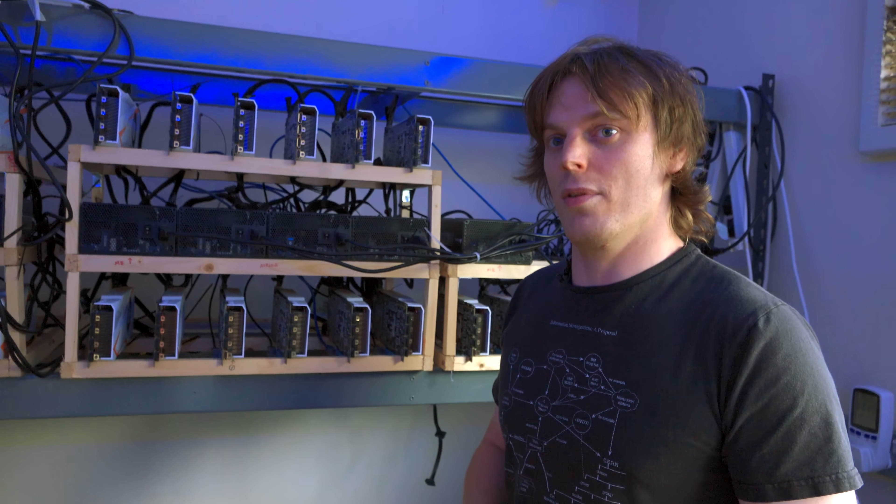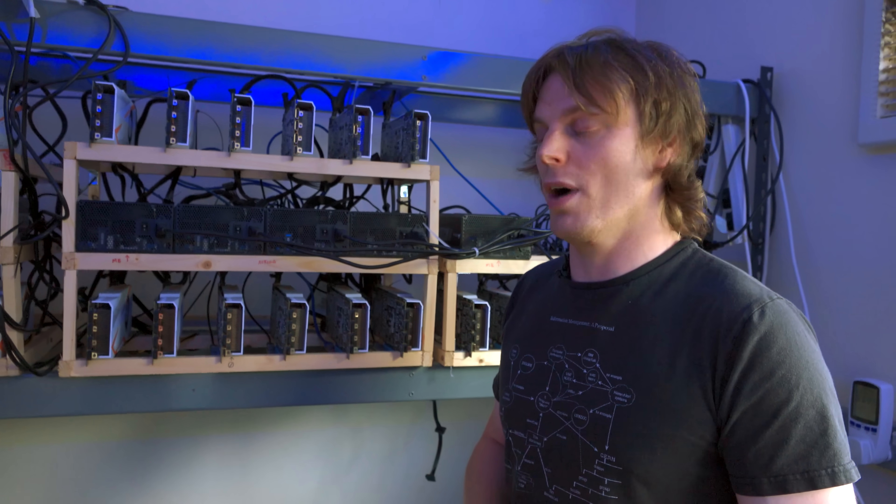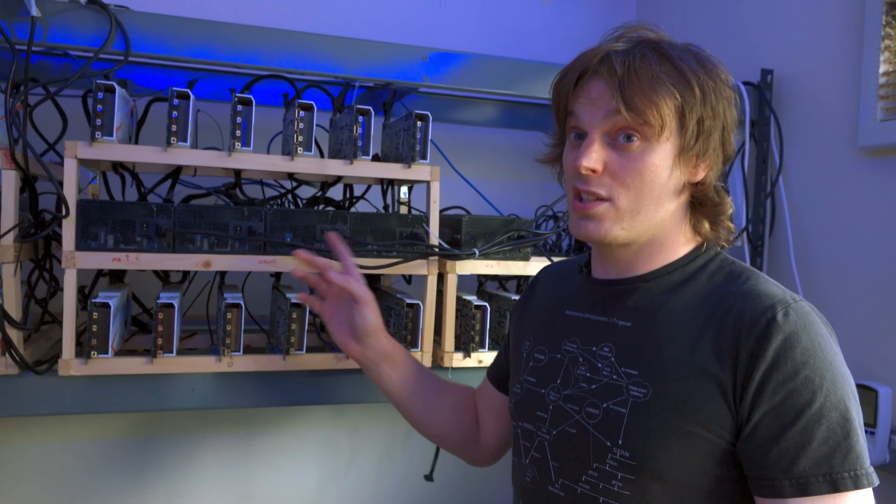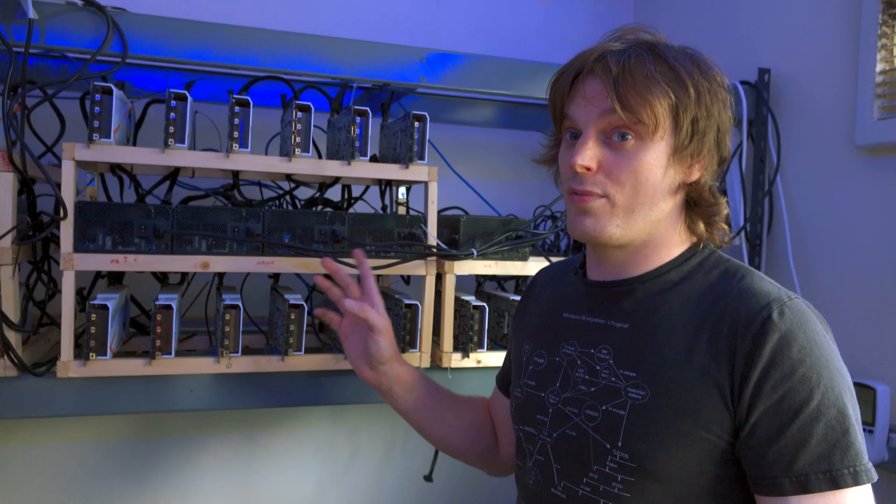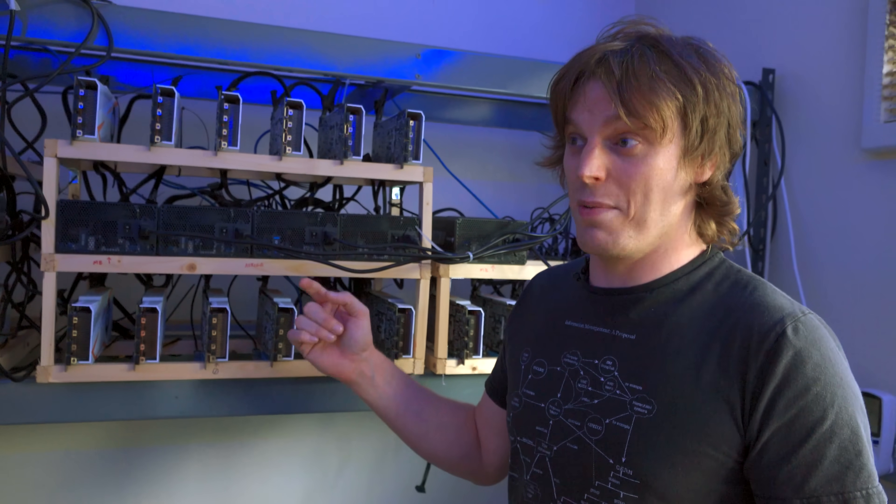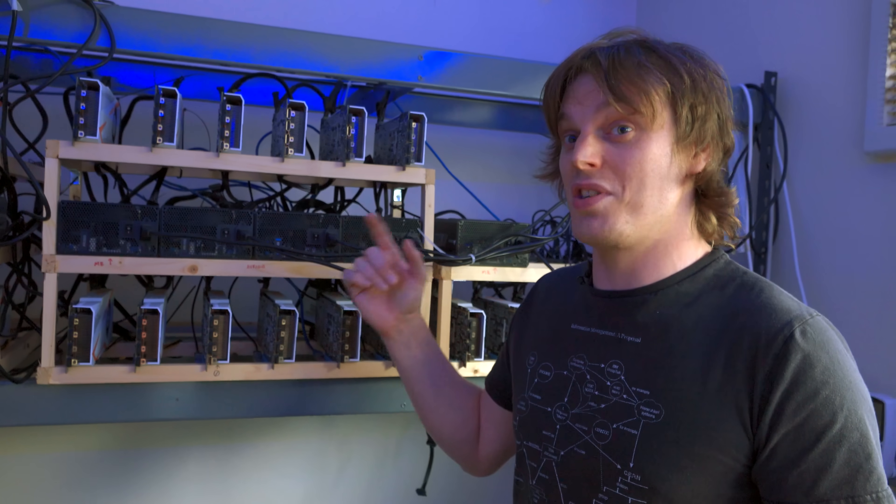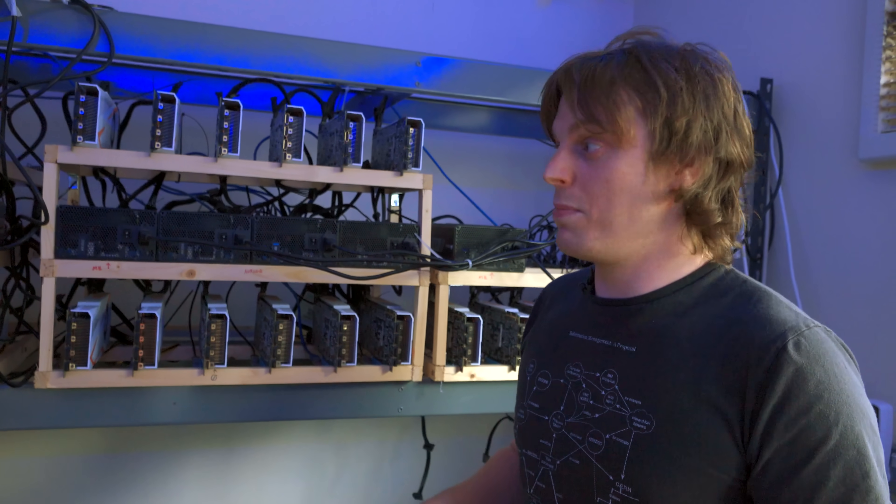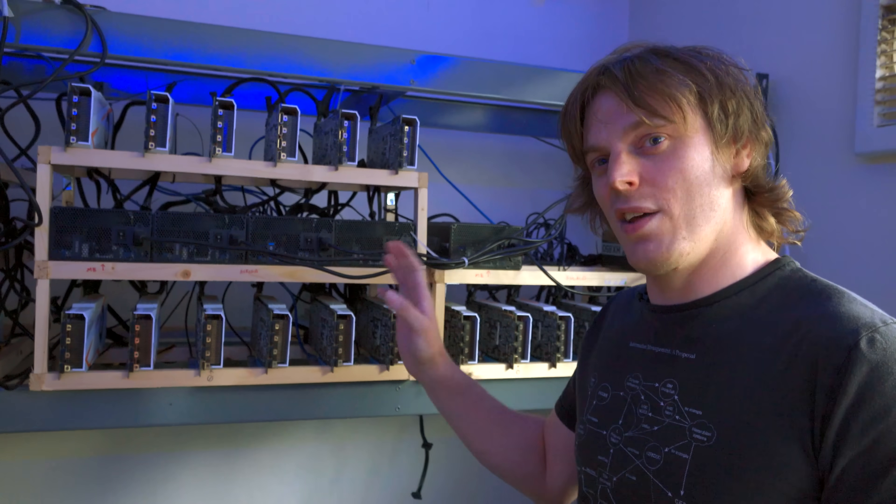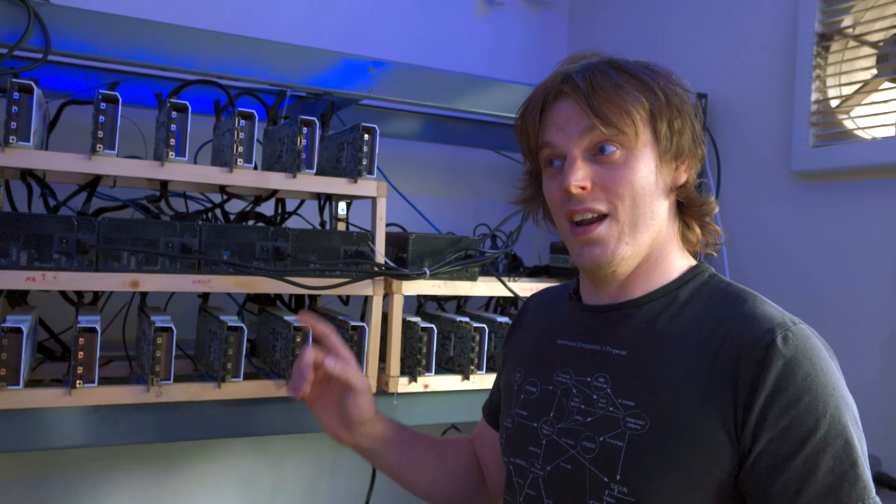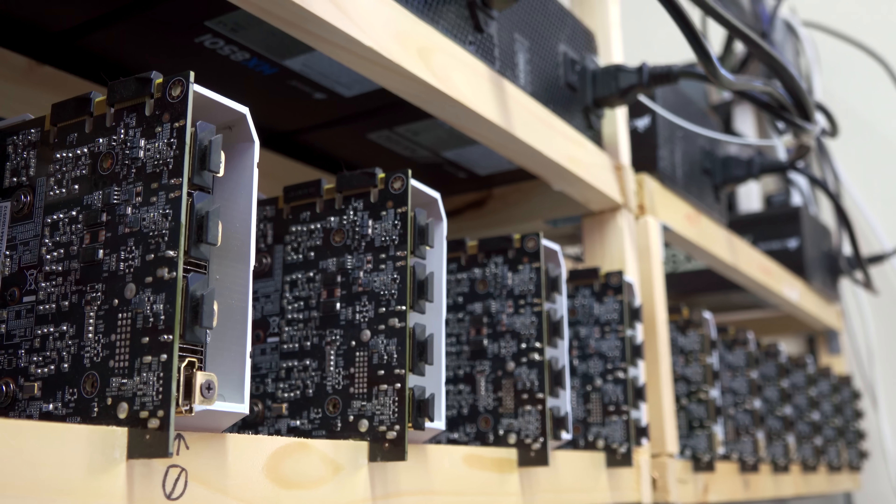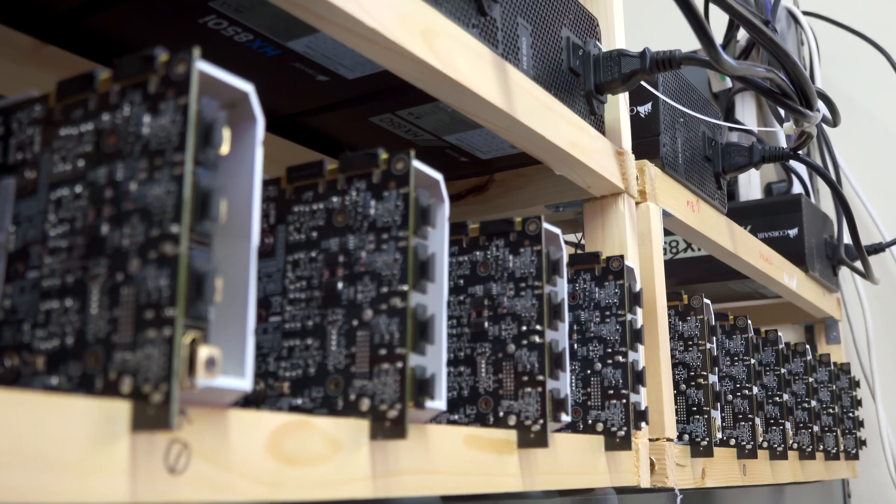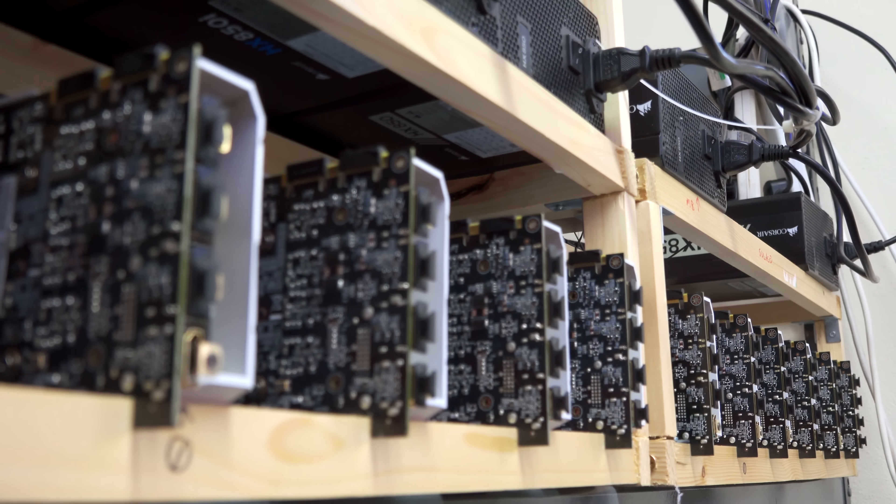Each of these cards is doing 250 watts of electricity in and converting the majority of that to heat. So we've got essentially a 15 kilowatt heater here in quite a small room, so we need to just keep that air moving as much as possible.